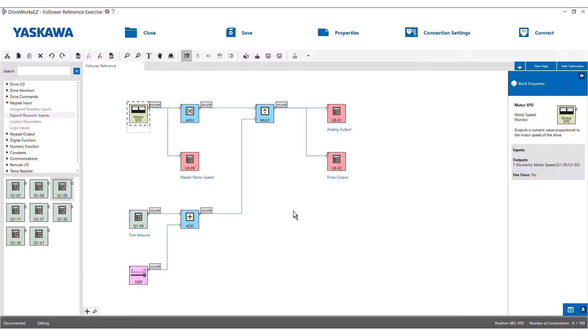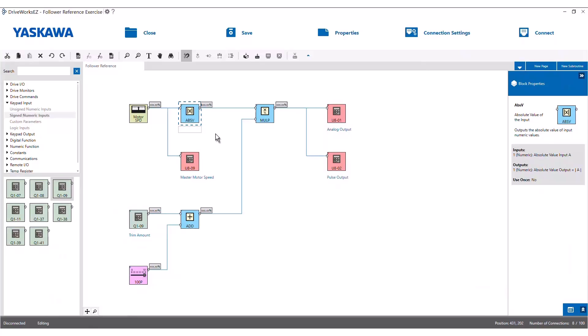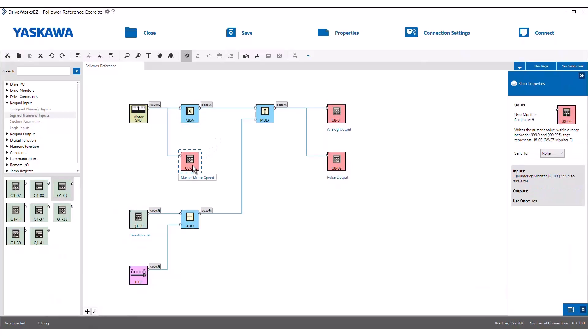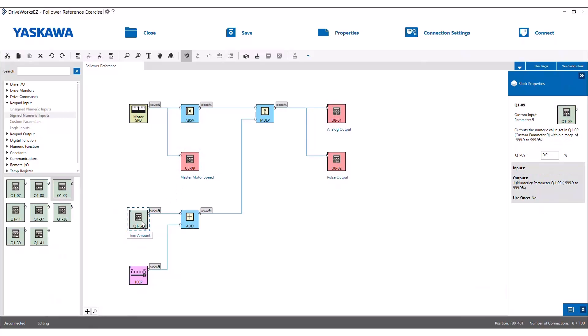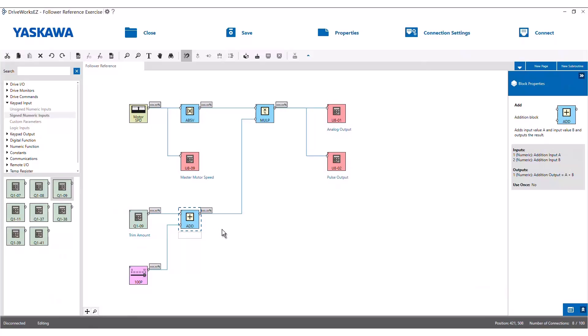Let's look at how we can utilize DriveWorksEZ to fill this application requirement. Starting in the top left we have our motor speed block — this is the motor speed of the GA500 drive demo unit we are connected to. That goes out to an absolute value block, which takes the motor speed whether positive or negative and always makes it positive, so the follower is always running in the forward direction. We tap off that motor speed block and set up a master motor speed monitor: U809 will display the master motor speed on the drive keypad. The blocks at the bottom right change our trim — Q109 is a keypad input for the trim amount that gets added to a 100% constant block, and the output of that add block goes up to a multiplication-by-percent block.